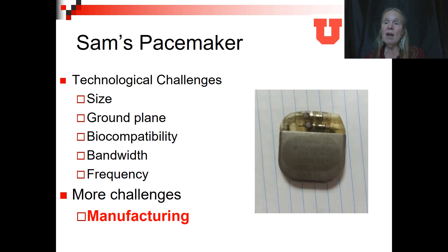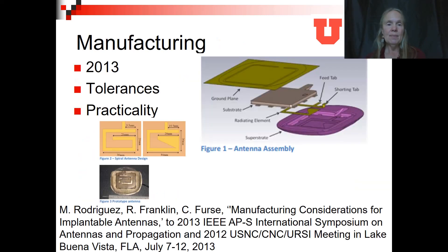Going back to Sam's pacemaker: after designing a number of these antennas, one serious problem limiting practical implementation was manufacturability. The challenge was taking materials that would not allow any biological fluid to enter them and trying to glue those onto titanium, which also resists being glued to. It was very difficult to keep these glued long-term without fluid seeping into the cracks. So in 2013, we worked out a different — backwards — design. The superstrate was first molded with a cavity into which the titanium antenna was placed, cut from titanium material like tinfoil. Then the pacemaker body was placed over that and the ground plane on top. This made a much more manufacturable design that could hold together with tabs instead of relying solely on glue.